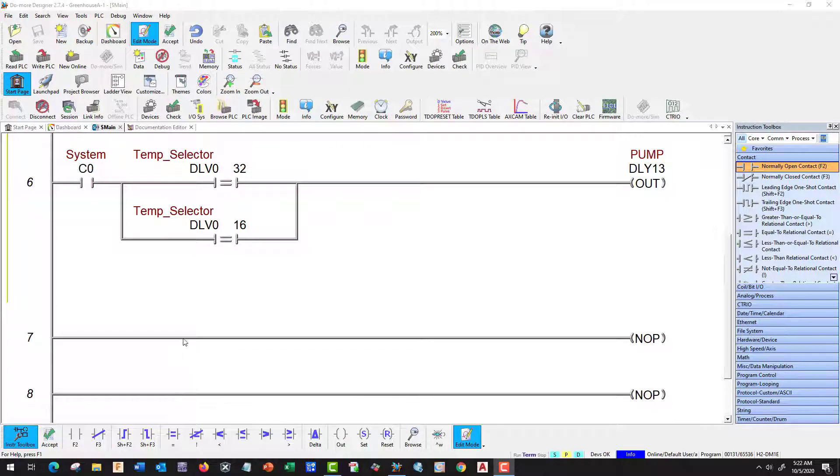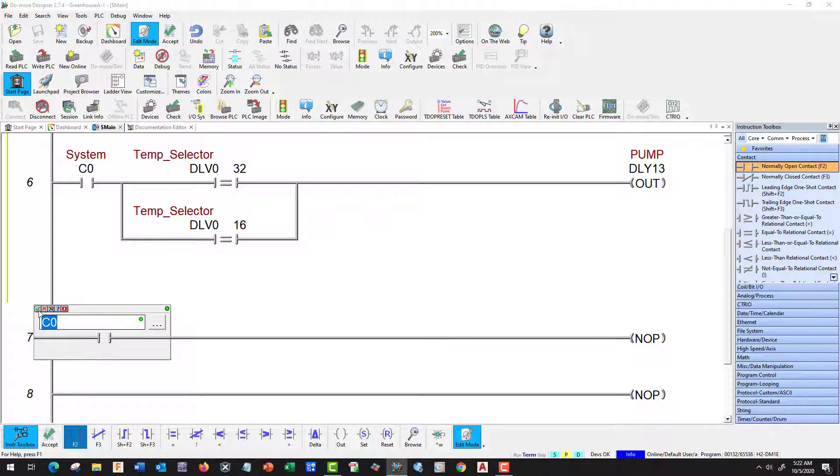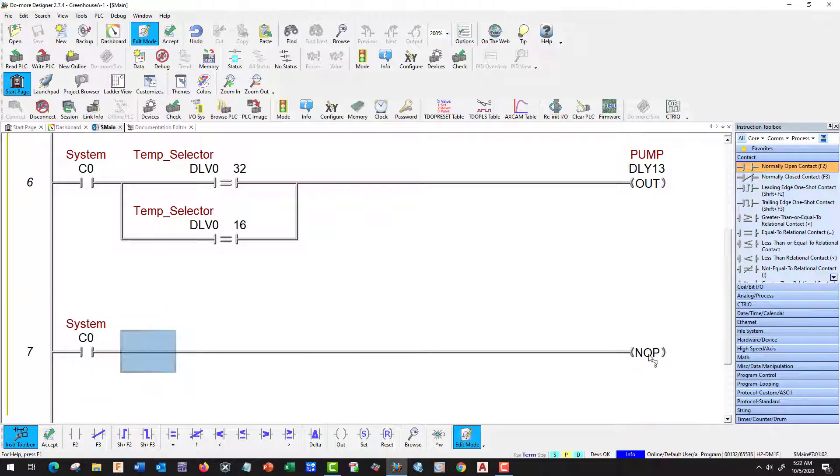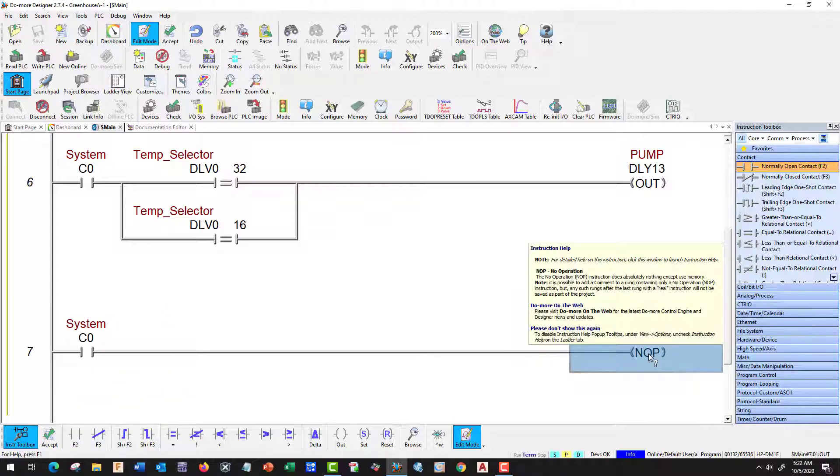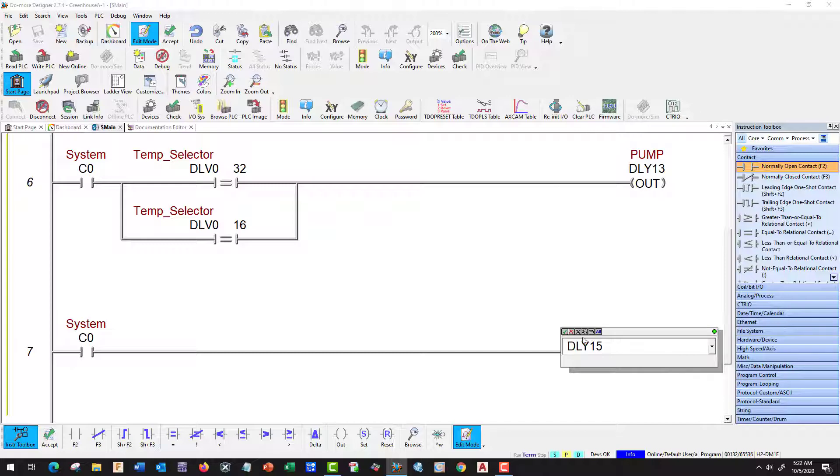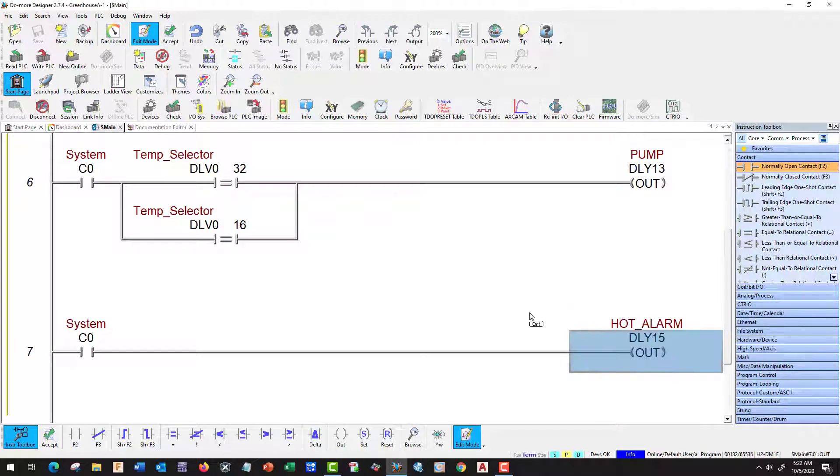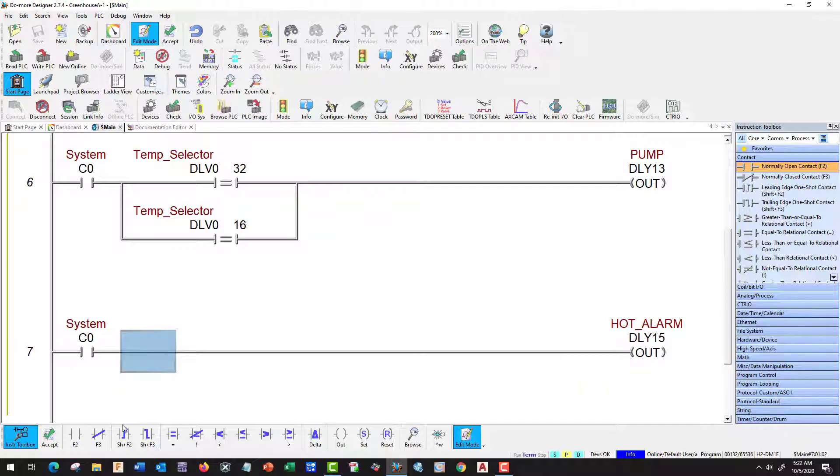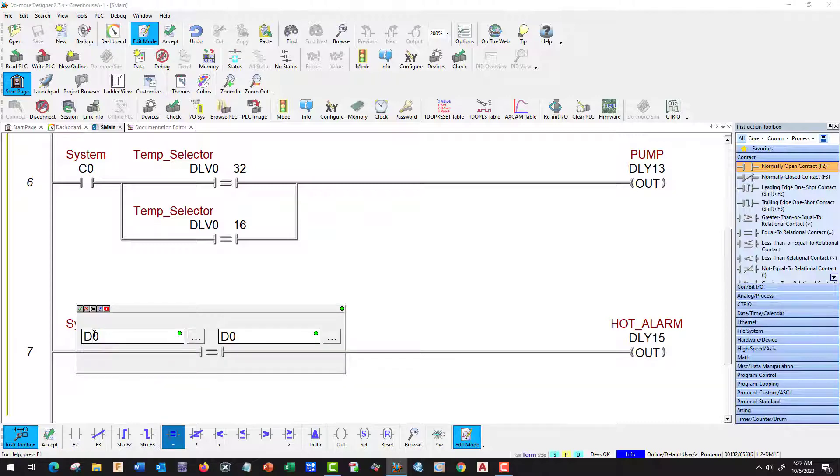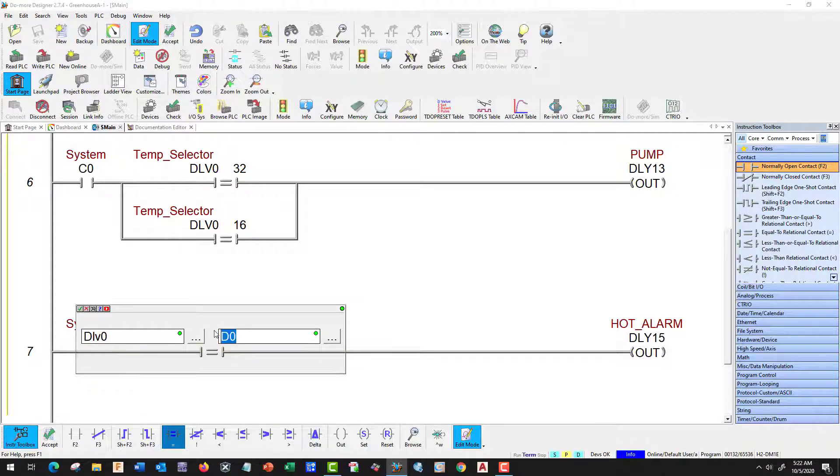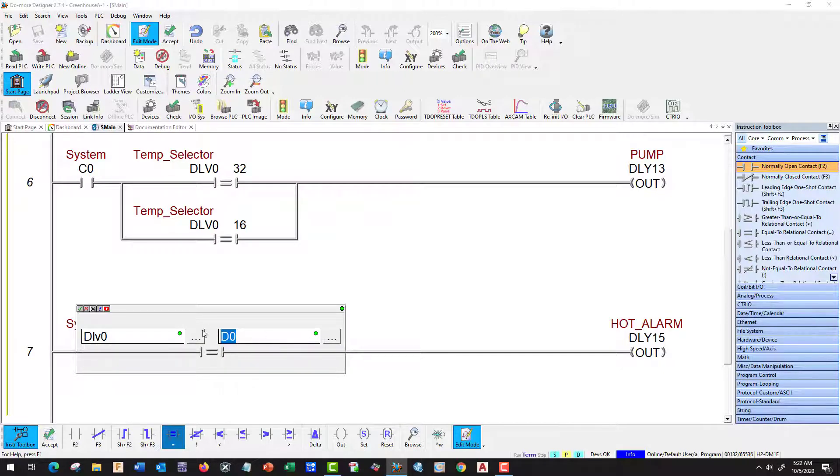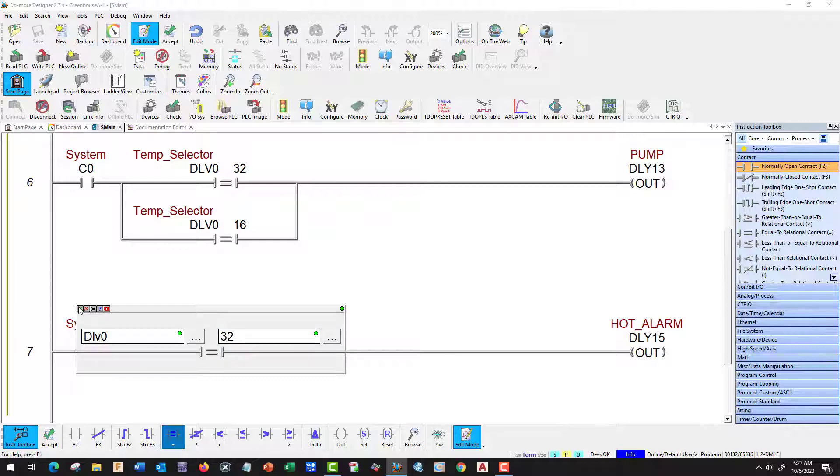Now let's take care of our heat alarm. We're going to need our control, System control. Our hot alarm is going to be DLY15. That's our hot alarm and it is going to come on when it's 100. So we're going to use our binary number from our radio switch, and 32 represents our switch. That should set our hot alarm.